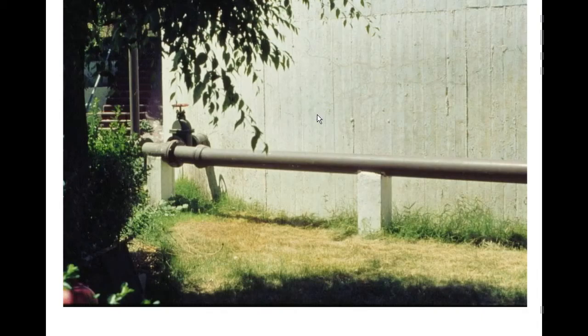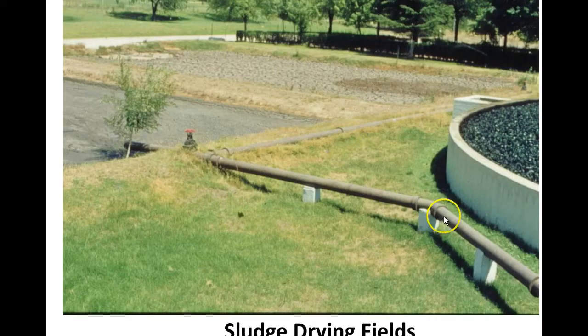So this then will leave, and I'll show you those pipes as to where it goes. But the sediment in these tanks, again, there's no oxygen there, so these things are breaking down anaerobically. There's no oxygen, and it forms sort of a thick paste, kind of a mud in a sense, that will be drained off from these tanks periodically through this pipe. And these were sludge draining pipes, and they go off to the sludge beds.